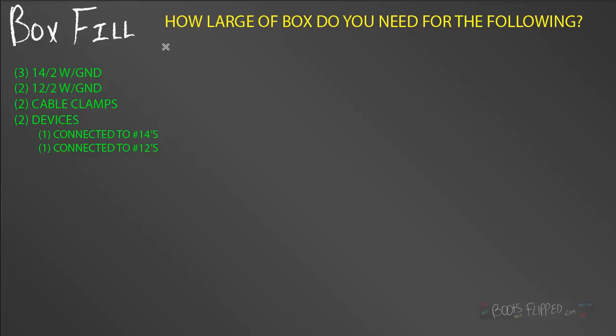Well, let's do this one. Remember, number 14s equal two cubic inch. And now I have another size wire, number 12s. And if we looked on our table, we know that the number 12s equal 2.25 cubic inch. So, let's start with this one. We have three 14 twos. So, I know that I have three cables times two wires each. That equals six wires times two cubic inch because they are number 14s. That equals 12 cubic inch. I can cross that one off because I've got more wires to deal with and we'll deal with our ground once we get to the larger one.